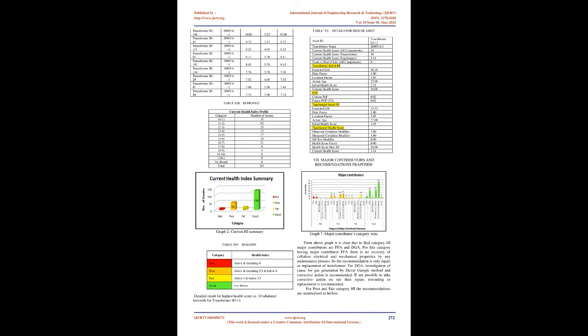Current health score: Having calculated an initial health score for all assets, we can now consider the available condition information in order to improve on, or override, the initial health score value. In order to calculate the current health score, the initial health score is multiplied by a health score modifier. The health score modifier is derived from a number of health score factors which are derived from condition information. For each condition measure, a minimum and maximum health score is also calculated, with the final health score being within these boundaries.